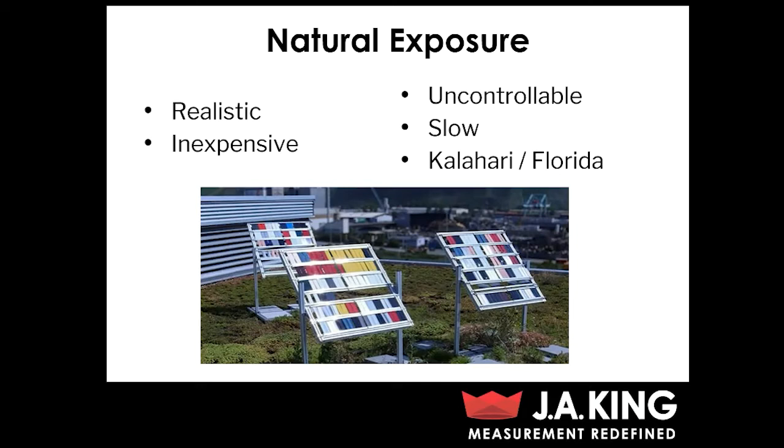I also wanted to point out that specifications typically focus on either dry or humid climates because that moisture content is going to affect the test results a bit. So typically specs either focus on testing in the Kalahari Desert for dry testing or in Florida for humid testing.